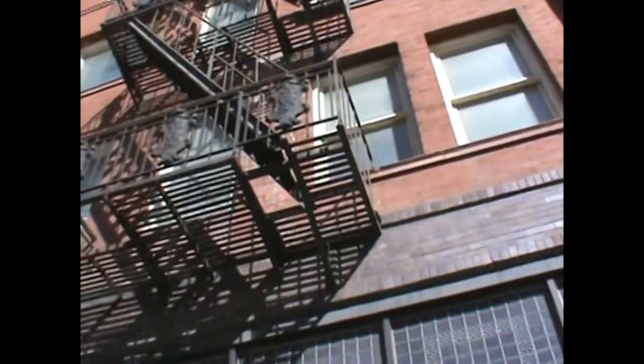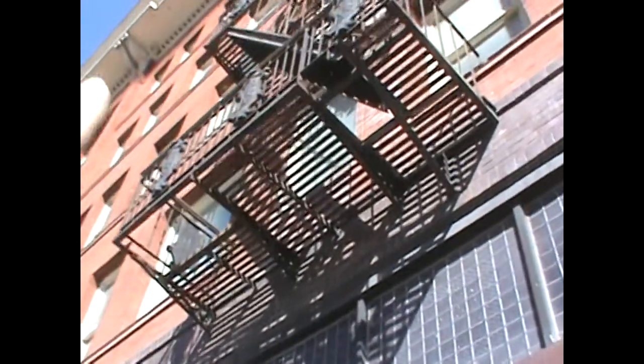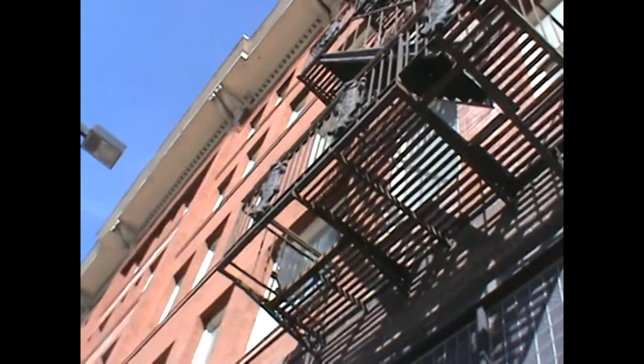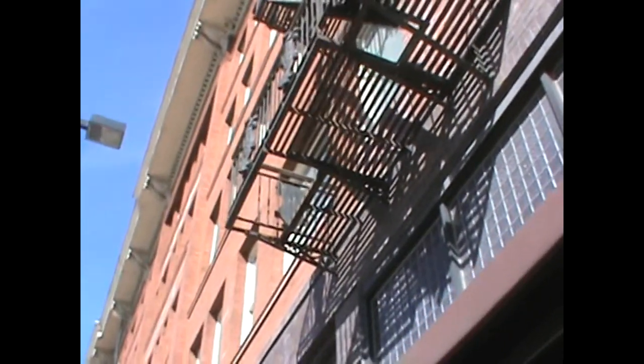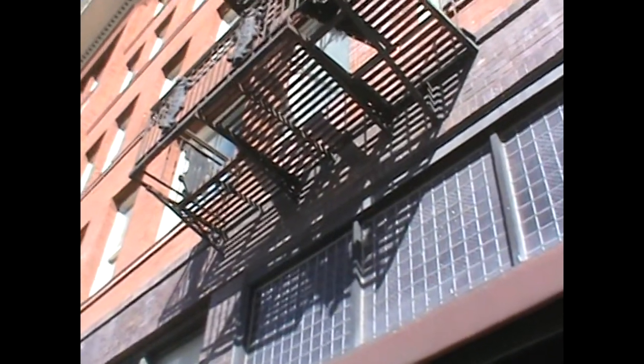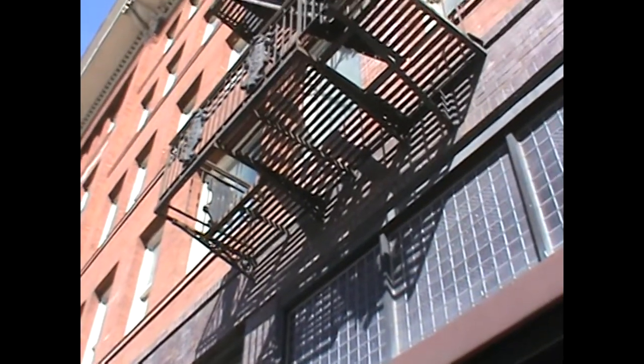All kinds of crazy things on this fire escape here. And the supports, look at the supports towards the ends. There's a bolt on the end of this support here, but if you go over to that support near the hole, do you see the bolt is missing? There's something missing there. Right. You see any new hardware anywhere on this fire escape? Not at all. So there's no evidence of maintenance. There's evidence of some painting, but it's been unpainted for at least 25 years, and because of that, they've exposed every connection, making every connection suspect.